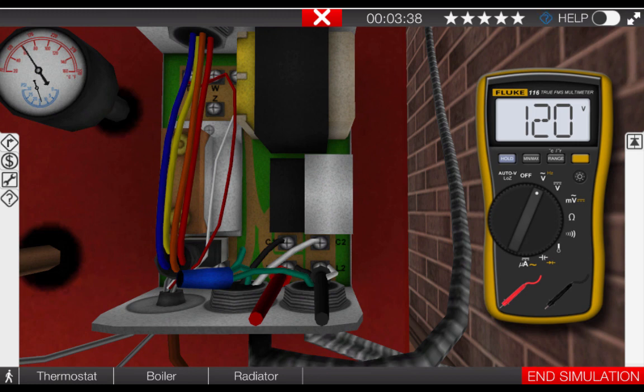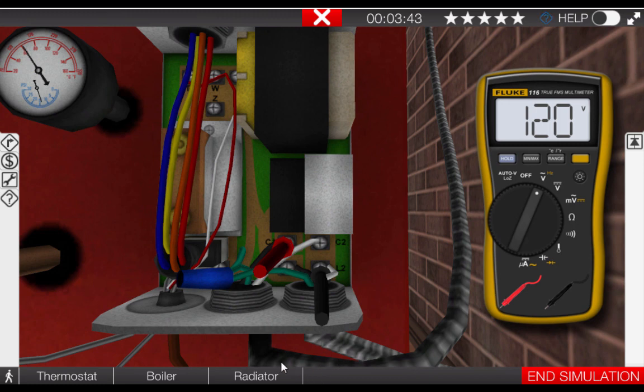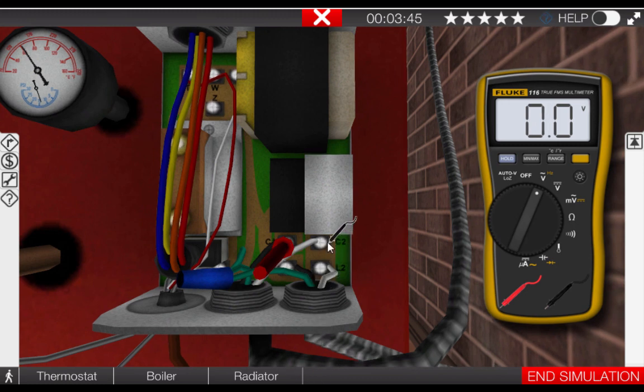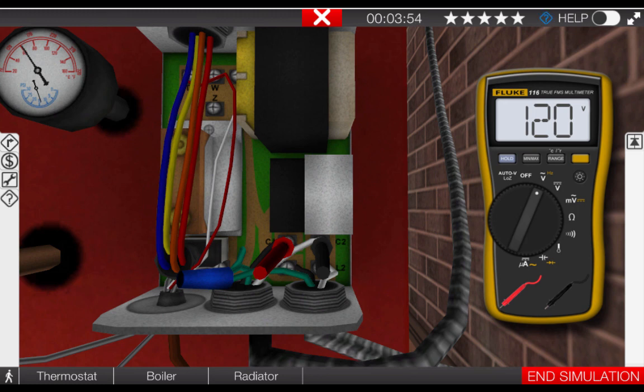Our next step is to verify that the combination aquastat is sending 120 volts to the circulator pump. This can be verified by measuring for voltage at the C1 and C2 terminals on the combination aquastat. Simply move the two meter leads to the C1 and C2 locations. Here we can see that 120 volts is measured, verifying that the aquastat is in fact sending 120 volts to the circulator pump.